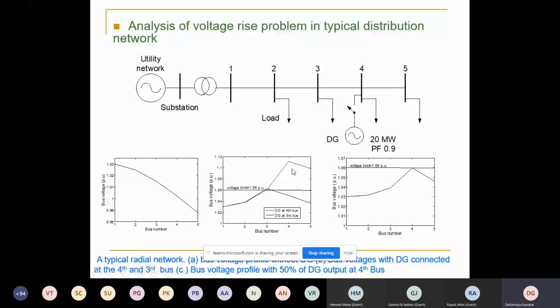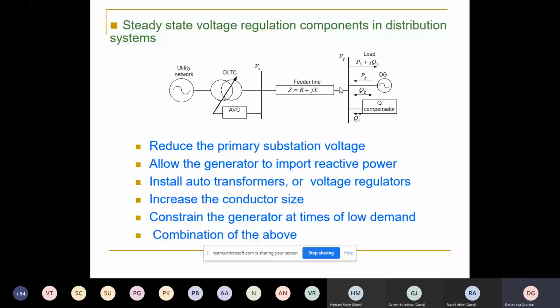Apart from that, there are several other things. If there is an issue, how do you control it? You have various methods to control the active and reactive power of DG. Use STATCOM, compensators, SVR, many things. Use load variation. Of course, varying the R and X of the line is not feasible, since you cannot keep replacing the conductor. Also vary the substation voltage using the tap changing transformer.